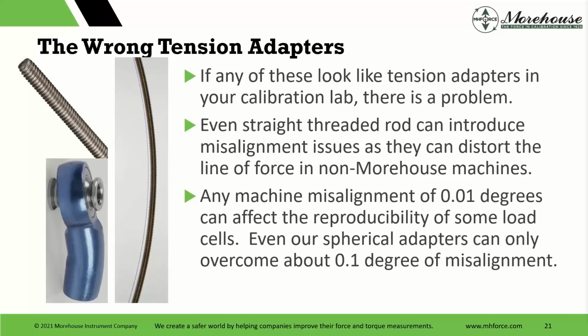Wrong tension adapters. If any of these look like a tension adapter in your calibration lab, there is a problem. Even straight threaded rod can introduce misalignment issues, as they can distort the line of force in non-Morehouse machines. Now, our UCMs, there's some other centering features that are in them. Deadweight machines sometimes have centering features depending on how you're loading it. And then any machine misalignment of 0.01 degrees can affect the reproducibility of some load cells. Even our spherical adapters can only overcome about 0.1 degree of misalignment.